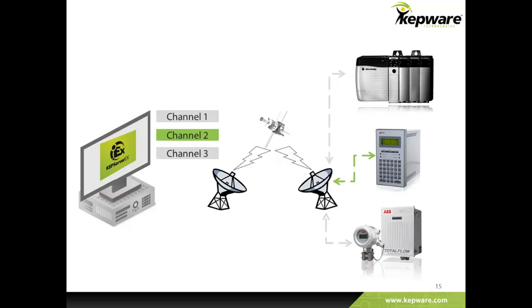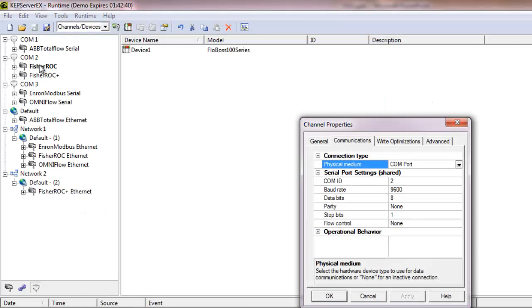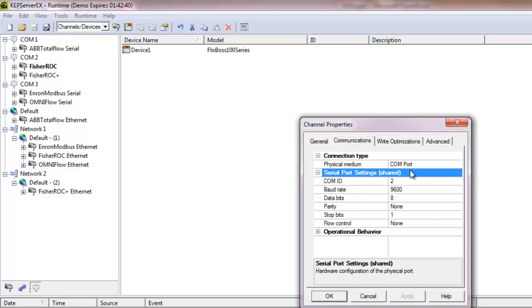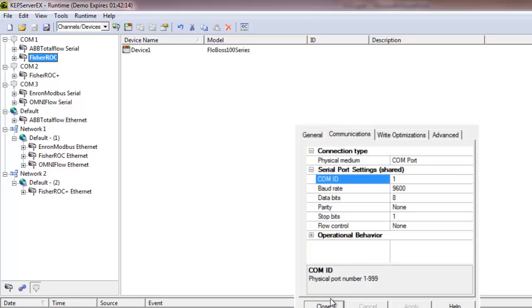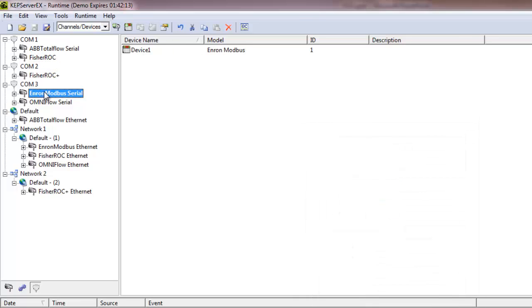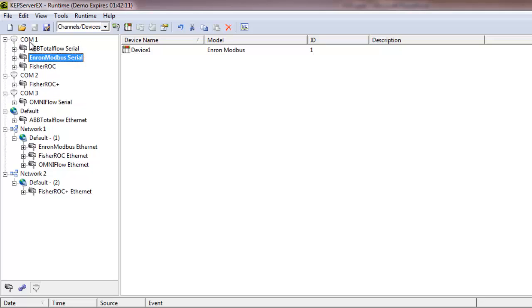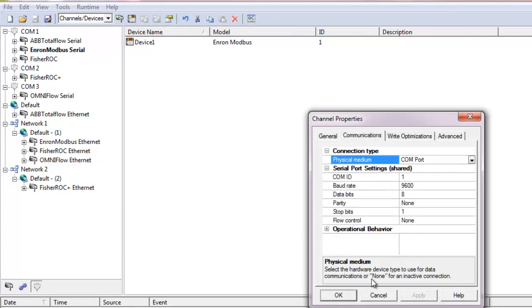KepServer EX enables drivers to share the same serial com port or to serialize communication over a network in order to meet this telemetry need. The connection sharing option allows channels of the same or different protocol to share a com port. Under serial port settings in the communication tab of the channel properties, the shared text will appear if the port is being shared with another channel. Remember users can drag and drop channels into connection groups as needed. The baud rate, data bits, parity, stop bits, and other com port settings must be consistent for all devices on the shared serial port. The user may specify up to 999 different com port connections in a single server instance.